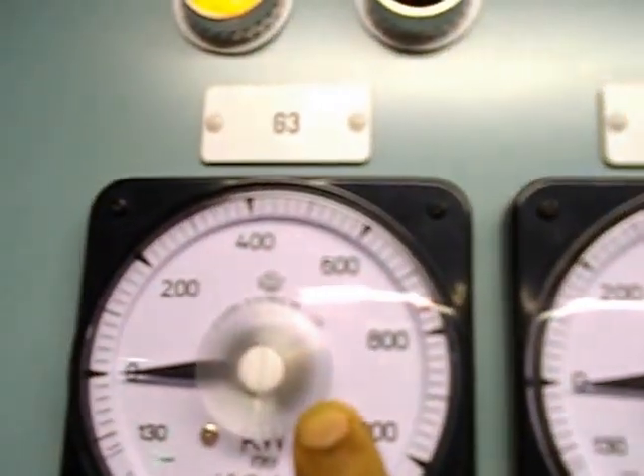Here we see the synchro panel. On the synchro panel we have kilowatt meters for generator number 3, generator number 2, and generator number 1. There is a frequency meter for the bus and for the incoming generator, and a voltage meter for the running generator and the incoming generator. This is the synchroscope. A dark lamp and bright lamp method is also provided as an alternative — so we have dark lamp, bright lamp, as well as the synchroscope.